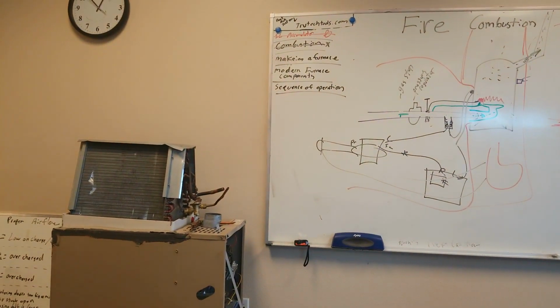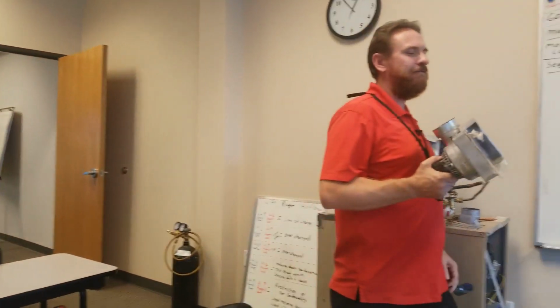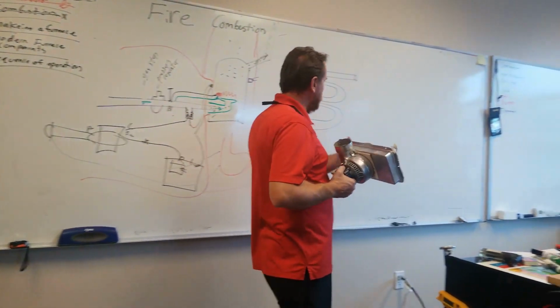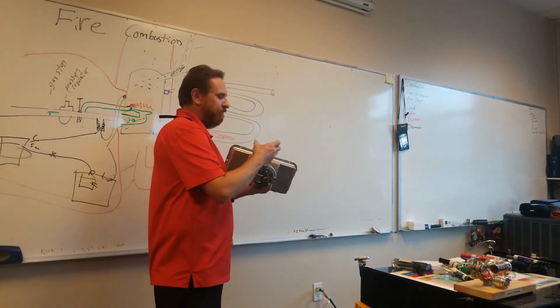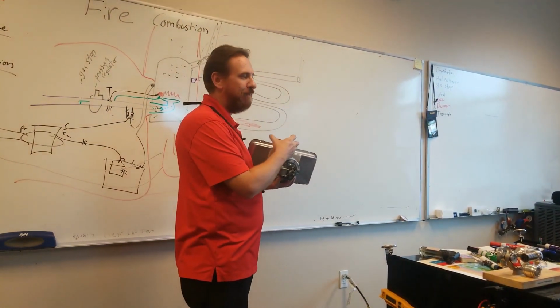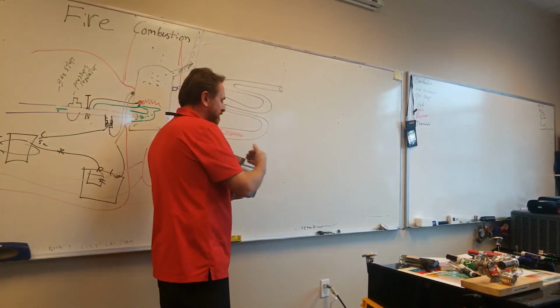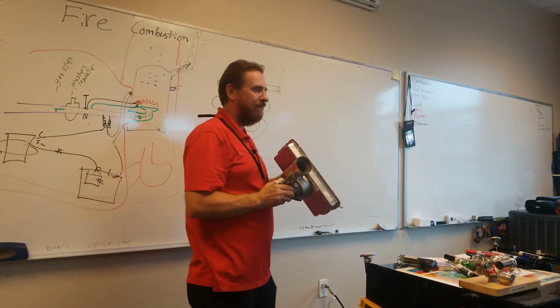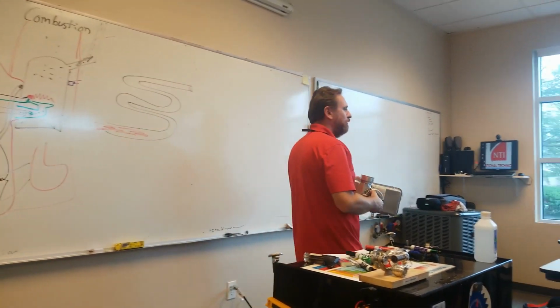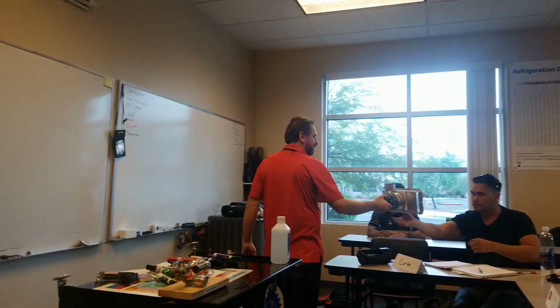Mm-hmm. So what we call that is an induced draft motor. We have one right here. This is an induced draft motor, where we're going to have multiple heat exchangers come together. This motor is going to pull that draft through it, and our chimney, which we're now going to call a flue pipe, is going to connect here. And we're going to pull a draft through it and force it out. And this is a metal blade. And it's the inducer motor, or a combustion blower, they call it sometimes. It's going to force a draft through that heat exchanger.